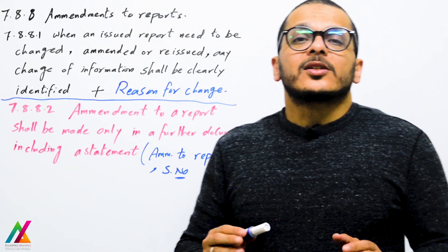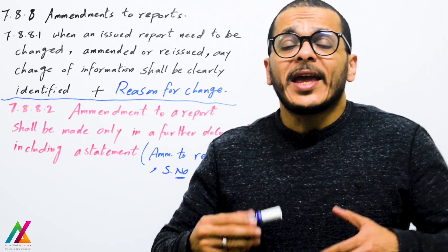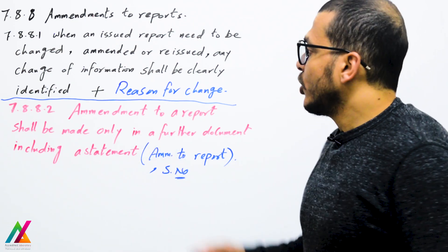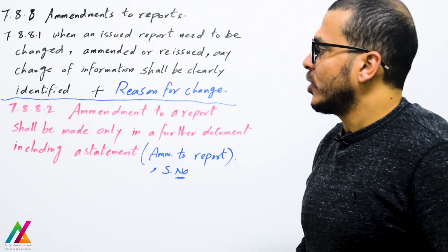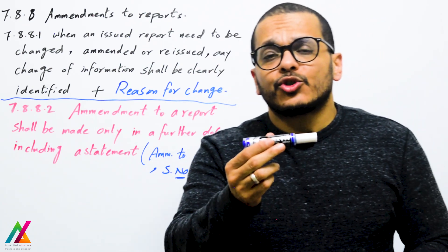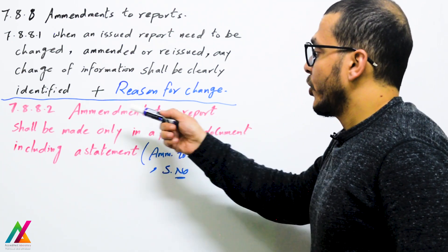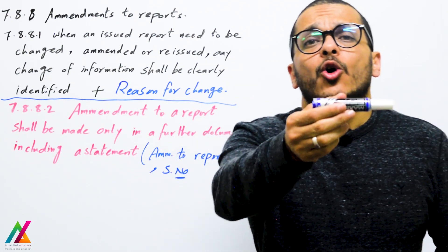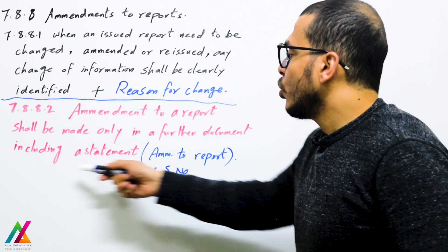The last point in reporting is amendment to reports — a very important topic. When an issued report needs to be changed, amended, or reissued, any change of information shall be clearly identified along with the reason for the change. However, an amendment to a report shall be made only in a further document — you cannot make all changes on the same report.